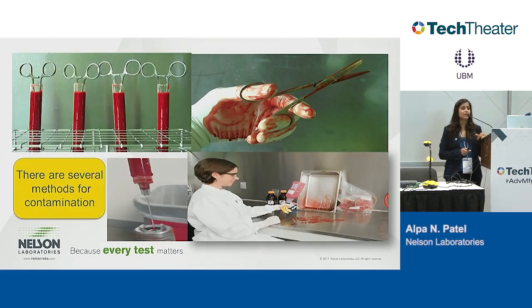These are some of the contamination methods that I use for clinical validations. Either you can do a full immersion, you can do spray, you can also do handling with soiled gloves, or direct inoculation, where we just use a syringe to directly inoculate the crevices or areas that are very hard to clean. A lot of the time, they are mixtures that we would use, where we would handle the device with soiled gloves, but the distal end of the device would be immersed in the fluid.